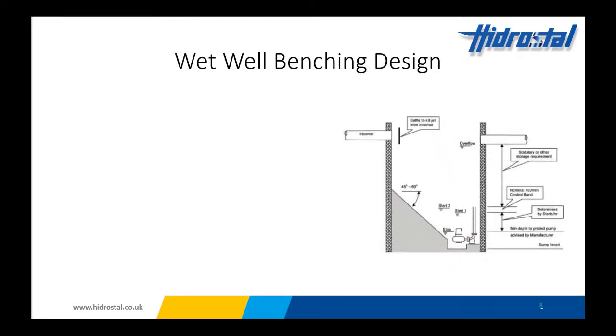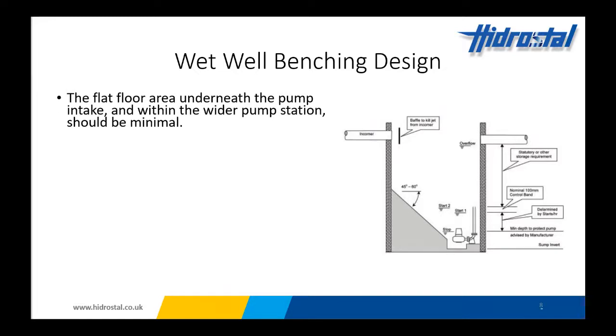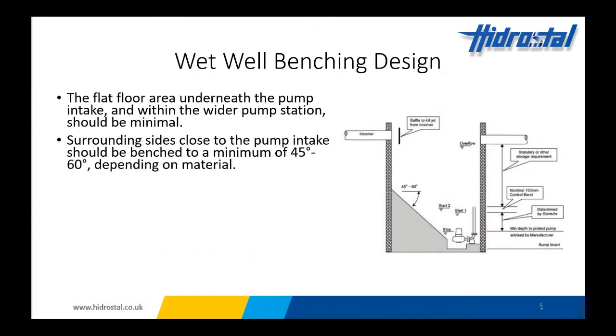Wet well benching: basically, the flat floor area underneath the pump intake, and within the wider pumping station for that matter, should be minimal. So that's this part here where it funnels down. Your stop level, ideally, you want to be quite low and have a minimum residual volume there. The surrounding sides should be benched 45 to 60 degrees. The rougher the surface, the steeper the bench. So concrete would work better with a 60 degree bench.